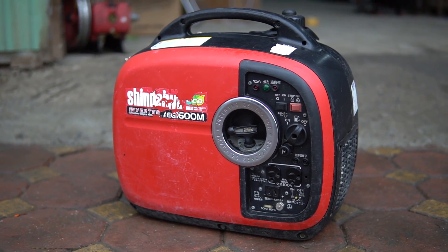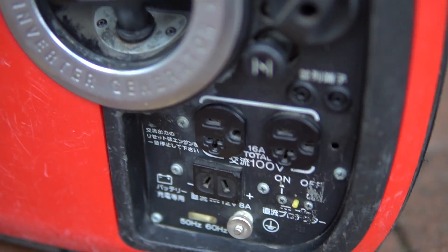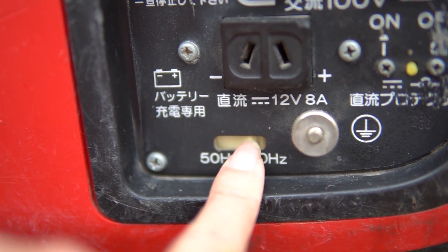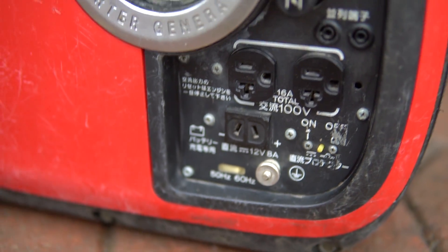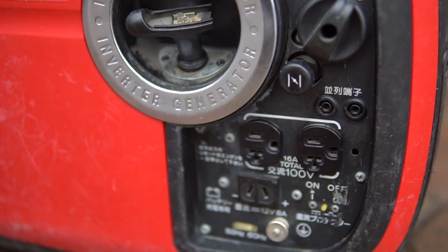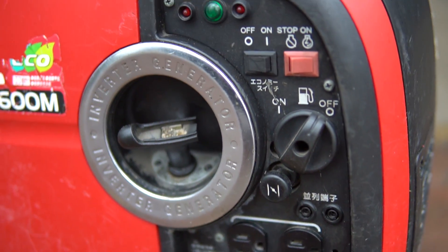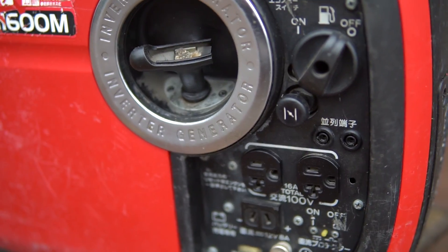Còn khi các bạn muốn chạy mắc tải thì tắt chế độ đó đi. Chiếc này còn có một điểm rất hay là chạy được ở tần số 50 và 60Hz. Các bạn có thể dùng một nút chuyển: khi chạy các thiết bị cơ thì sử dụng tần số 60Hz để ga to lên, công suất ra khỏe hơn. Còn khi chạy các thiết bị điện tử, điện lạnh thì nên sử dụng tần số 50Hz.